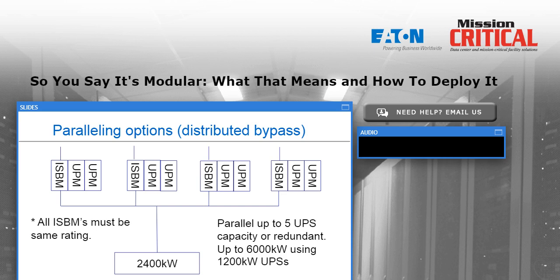And if I have a single lineup, let's say I have 4 UPMs in one long black cabinet, and I say, gee, I want to dedicate 2 of them to an A side UPS and 2 of them to a B side UPS. That's certainly a good idea, but the problem is we have no way to do that mechanically. So what we would recommend is set up a 2 UPM system on the A side and a separate 2 UPM system on the right side, so that I would have some literal and figurative space between those systems, so they're completely isolated from each other, both electrically and physically.